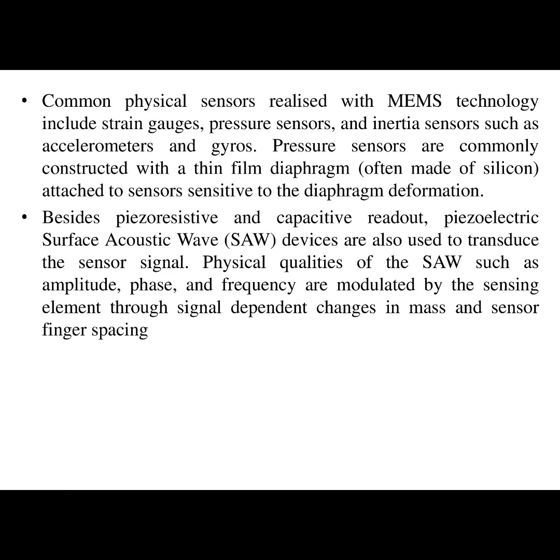Besides piezoresistive and capacitive readout, piezoelectric surface acoustic wave (SAW) devices are also used to transduce the sensor signal. Physical quantities of the SAW, such as amplitude, phase, and frequency, are modulated by the sensing element through signal-dependent changes in mass and sensor finger spacing.